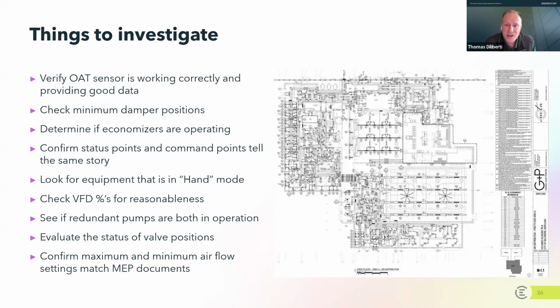Make sure it's not in the sunshine. Make sure it's being protected, so it doesn't get any type of false readings, because that one simple sensor can have a wildly different effect in your building if it's not behaving properly. Check those damper positions to be sure they're right. Look at your economizers. Make sure those status points and command points are telling you the same story. Again, check the VFDs for reasonableness, those redundant pumps, and the valve positions.